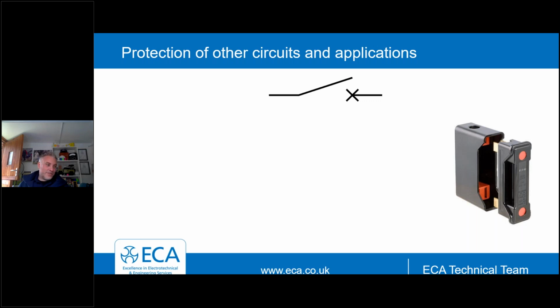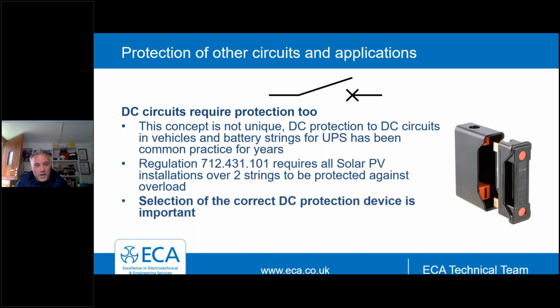Do we need to protect other circuits? Yes, absolutely. DC circuits require protection too. Okay, so battery strings, even battery storage in homes, you'll quite often see that if it's more than one battery, it will require you to put effectively a DC fuse box in. Okay, typically with DC, we are looking at, I guess, the good old BS88 fuse, which is a robust fuse, takes power flow in both directions. But there are others, and it's worth knowing actually that our 60898, our traditional ordinary person's circuit breaker, our MCB, isn't commonly used on DC. We need to move towards the 60947-2 circuit protection for DC and confirm with the manufacturers that they're suitable. So, these devices are built for DC. It's really important that we get the right protection for our DC circuit.